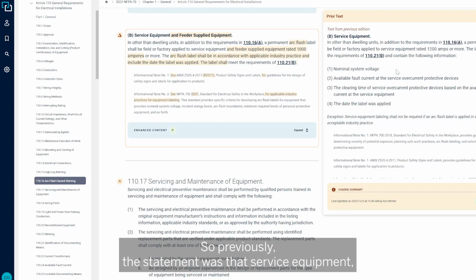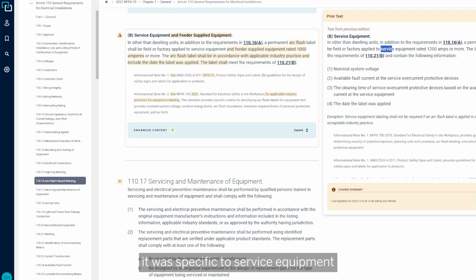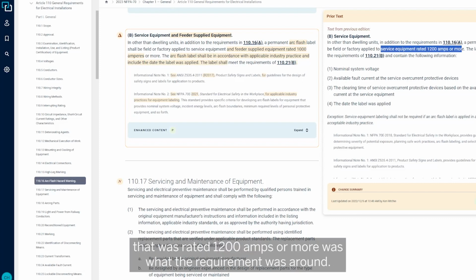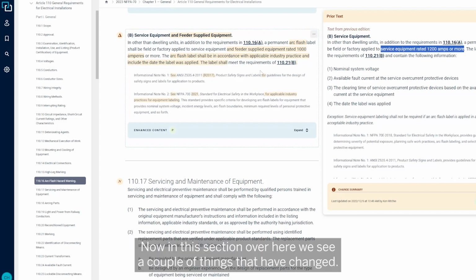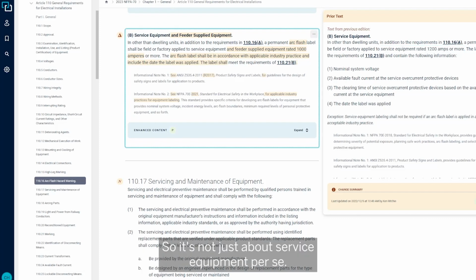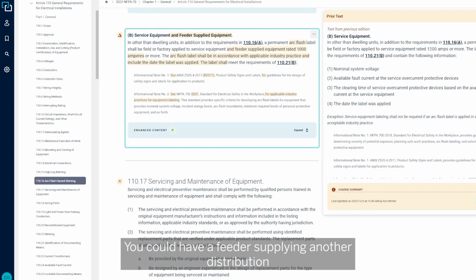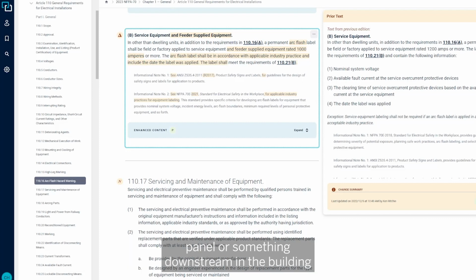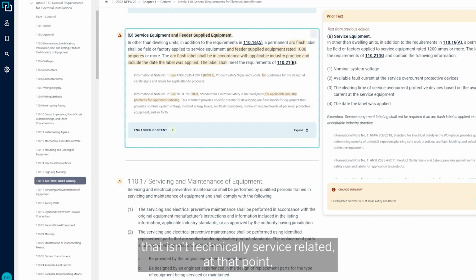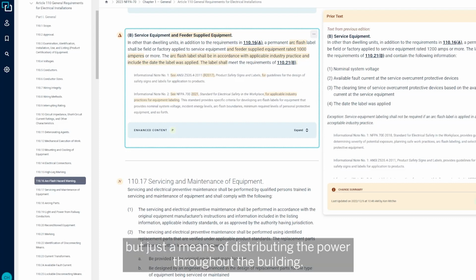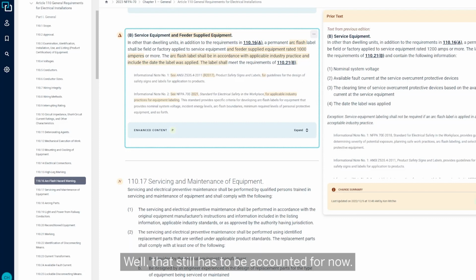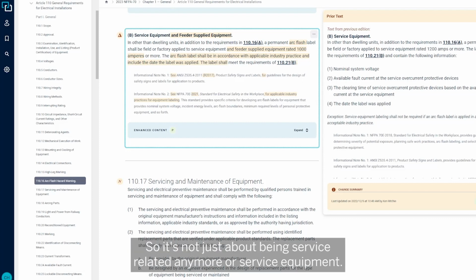So previously, the statement was that it was specific to service equipment that was rated 1200 amps or more was what the requirement was around. Now, in this section over here, we see a couple things that have changed. We now have feeders. So it's not just about service equipment per se. You could have a feeder supplying another distribution panel or something downstream in the building that isn't technically service related at that point, but just a means of distributing the power throughout the building. Well, that still has to be accounted for now. So it's not just about being service related anymore or service equipment.